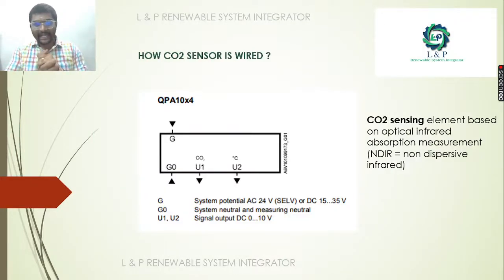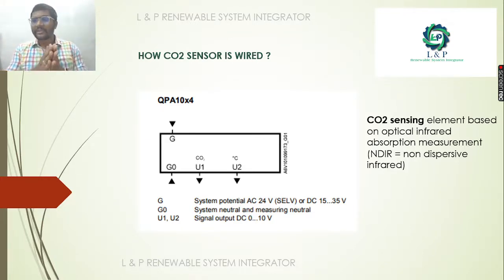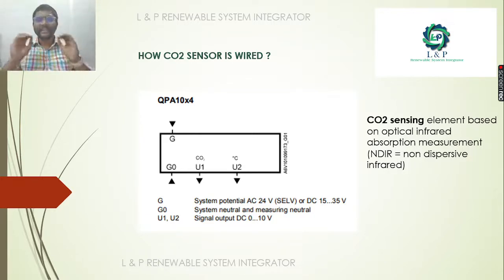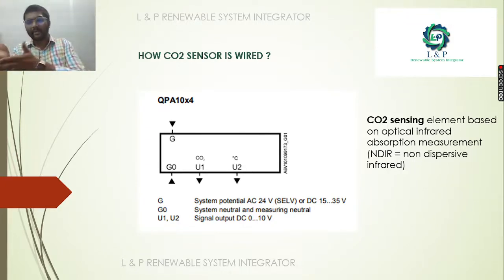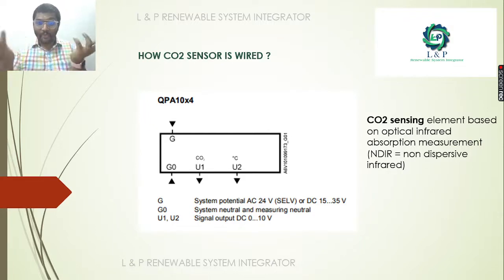This is a wiring diagram of a CO2 sensor — the Siemens QPA10X4 series. It works based on optical infrared absorption measurement. For this sensor, no calibration is needed. The sensor needs an operating voltage — it can be AC 24V or DC 15 to 35V. In the G and G0 terminals, we will connect the operating voltage. To take the feedback, we have two options: U1 and U2.